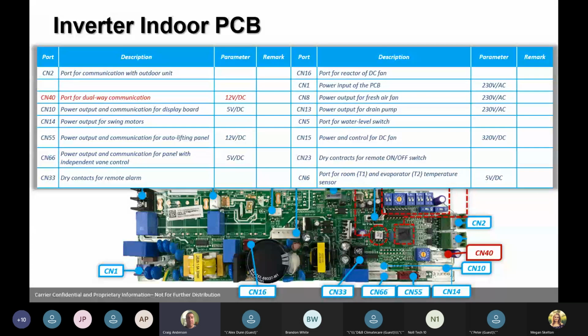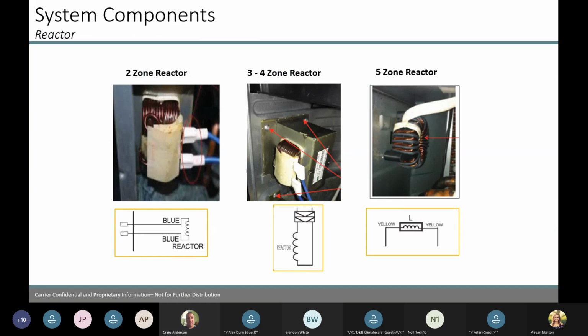So you'll see reactors in the system on some of the main systems. This is cleaning the power before it goes into the DC circuit. If a reactor has failed, we could get a communication fault because the voltage isn't going through it. So it's going to tell the unit, well, I can't talk because something has happened. The reactors look like a little coil. There's usually a couple blue wires hooked up to them.